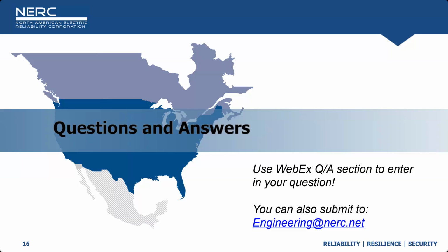I'll start by saying that primarily, if you can get a distribution PMU or some other recording device installed on the facility, that will greatly assist in identifying risk associated with that facility for disturbances. I think one of the major recommendations here is for communications and disturbance recording to be installed, in addition to other things the TOs would want as part of their interconnection requirements, processes, and procedures.